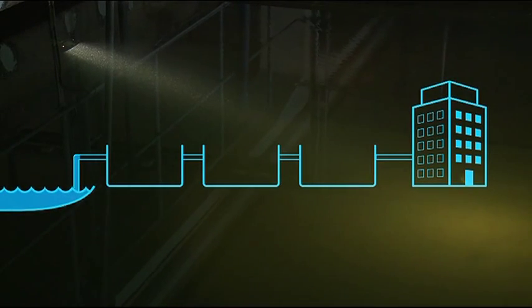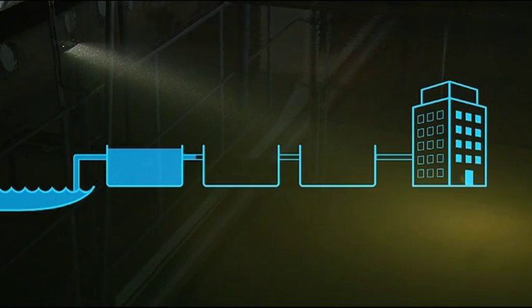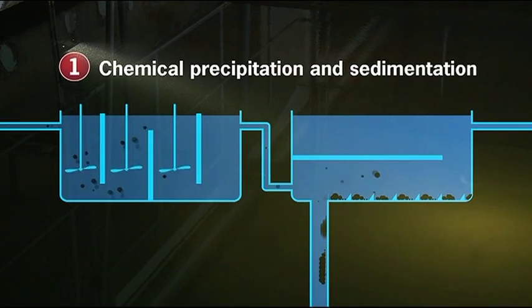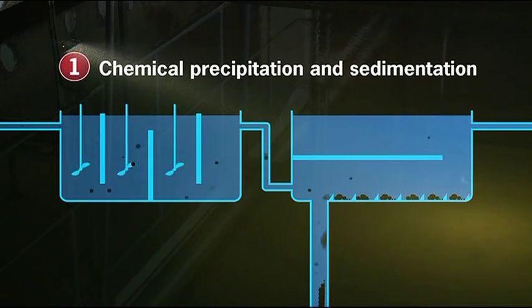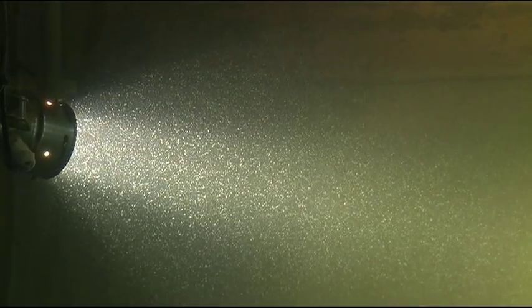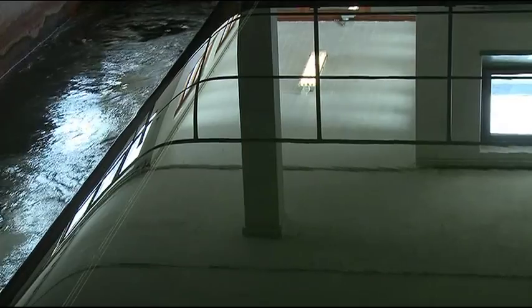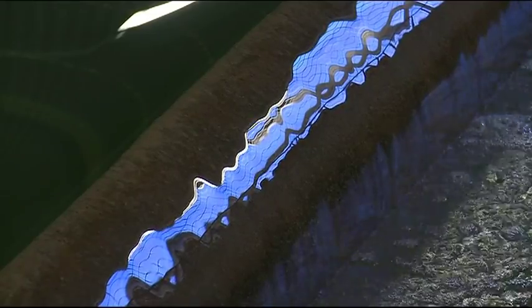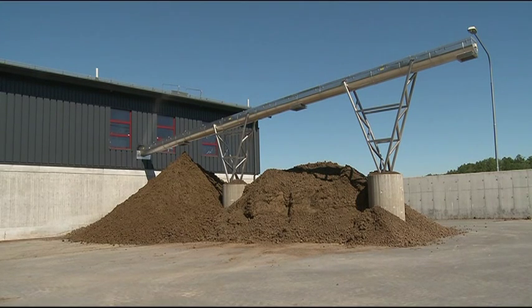The water now passes through three treatment stages: a chemical, a mechanical and a biological stage. During the chemical treatment stage, a small quantity of aluminium sulphate is added. This functions as a precipitation agent and flocks are formed, which absorb the small particles present in the lake water. The water is passed slowly through a sedimentation basin. Most of the flocks sink to the bottom and are separated in sludge form. The sludge is de-watered and can then be put to various uses.